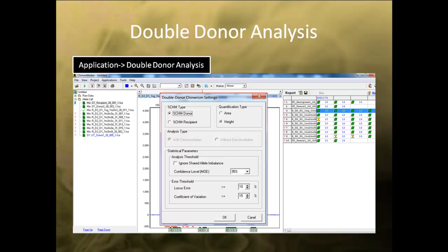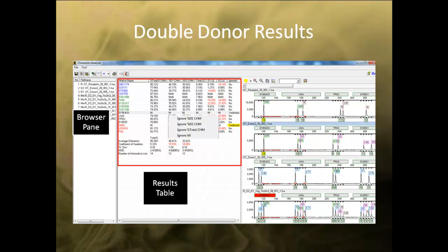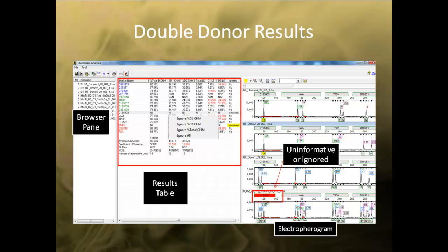To begin quantification, click on the Application tab and select Double Donor Analysis. All settings are described in detail in the introductory webinar. Click OK to begin quantification. The analysis will display the quantification results in the middle pane. The results will give you total donor percent chimerism as well as an estimated value for each individual donor contribution. The yellow color in the Ignore column indicates the markers that are not used in the quantification, done either by selection of SAI or right-clicking on a particular marker and choosing to ignore it. You can navigate to each individual sample using the browser pane on the left, and the electropherogram for the selected sample will be displayed on the right side. Any markers with a red color code are either ignored or uninformative. You can use the help menu on the upper right-hand side for an explanation of each parameter.